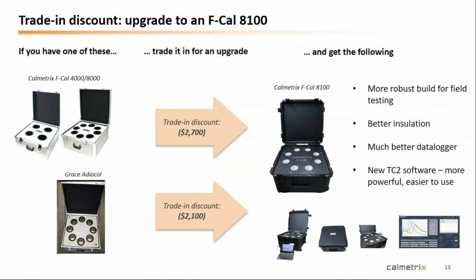If you have an F-Cal 8100 already — the black-cased unit — you can download the new software; it's a free upgrade. When you install it, you'll get a second icon on your desktop for the new Thermal-Cal, alongside the existing Cal Commander icon. You can open data files generated in the old software using the new software. However, data generated with the new software cannot be opened in the old software — it's upgradeable forward only, not downward. Any data files generated in the new software cannot be opened back in the old software.